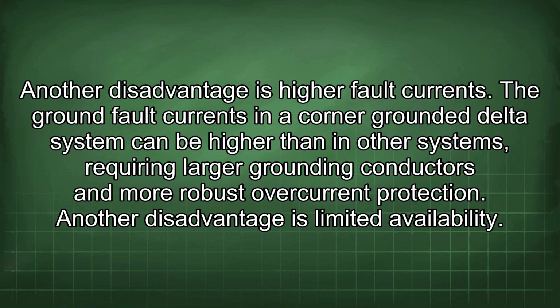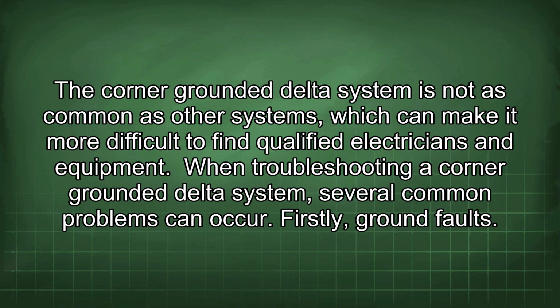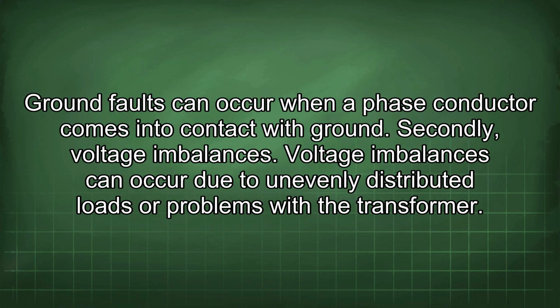Another disadvantage is limited availability. The corner-grounded delta system is not as common as other systems, which can make it more difficult to find qualified electricians and equipment. When troubleshooting a corner-grounded delta system, several common problems can occur. Firstly, ground faults. Ground faults can occur where a phase conductor comes into contact with ground.